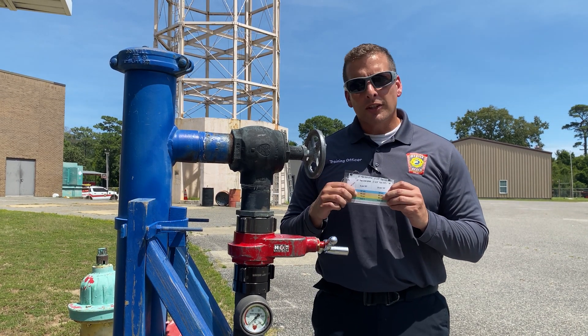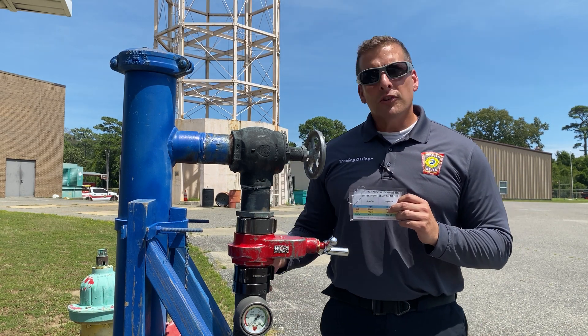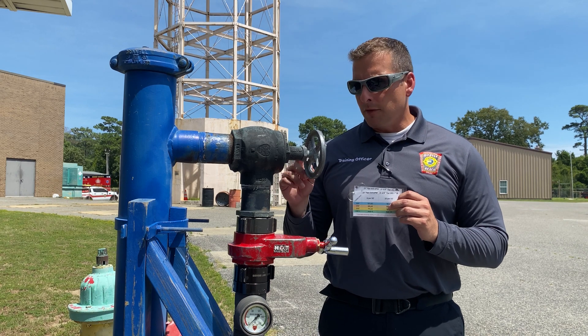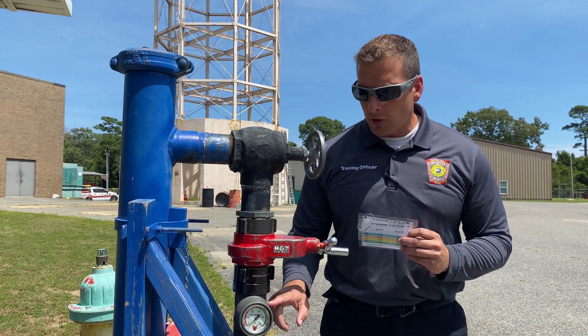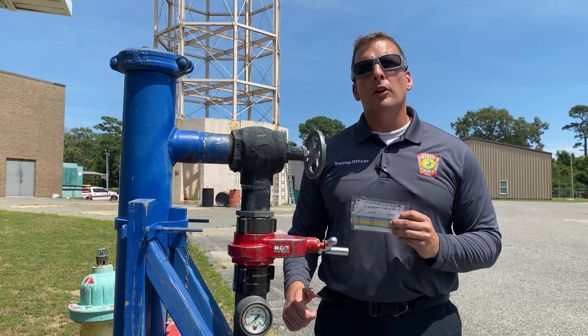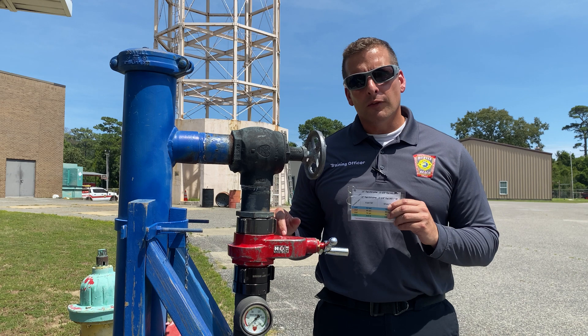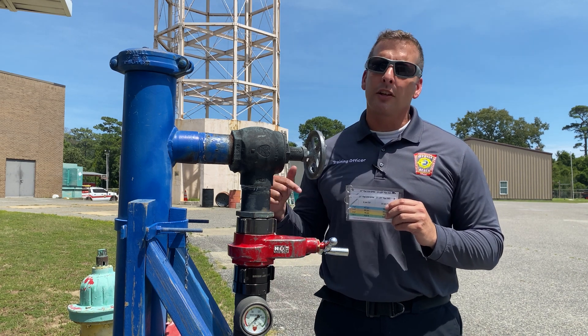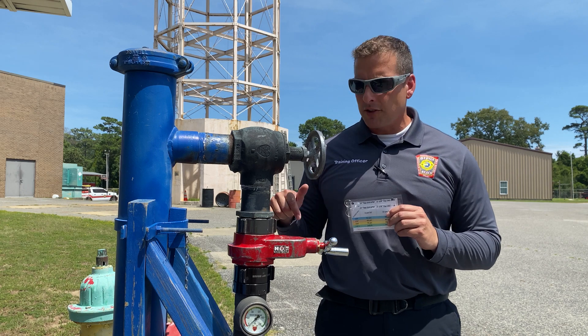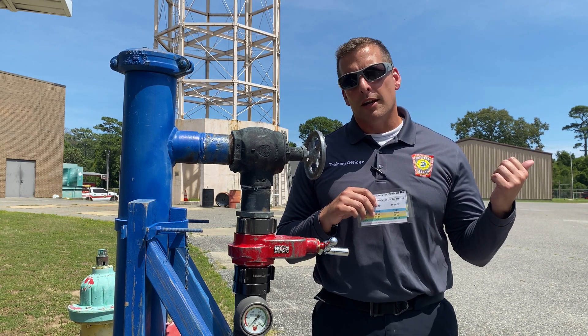This quick reference guide's numbers are to be set for the outlet pressure when flowing. When you open these building systems up at the valve and you don't have any water flowing out of your nozzle, these pressures are going to reach static pressures that may be really high — higher than what the number you need. That may give you a false sense of hope and may cause you to over-pressure or have a significantly under-pressurized system, which is going to hamper your flow rate at the end of the line.